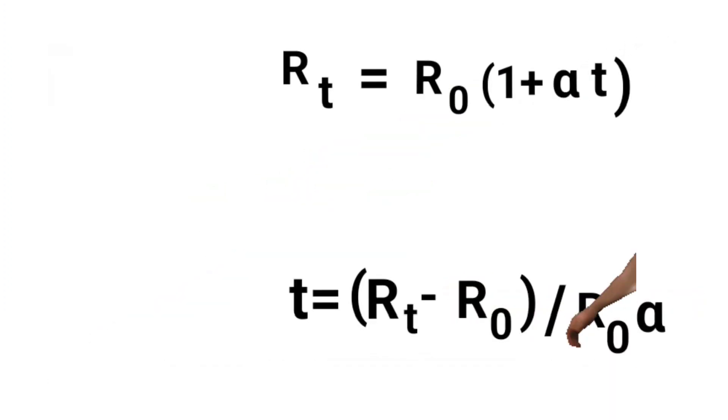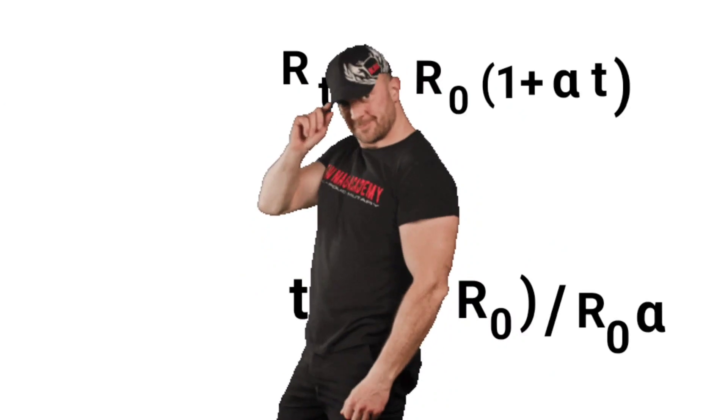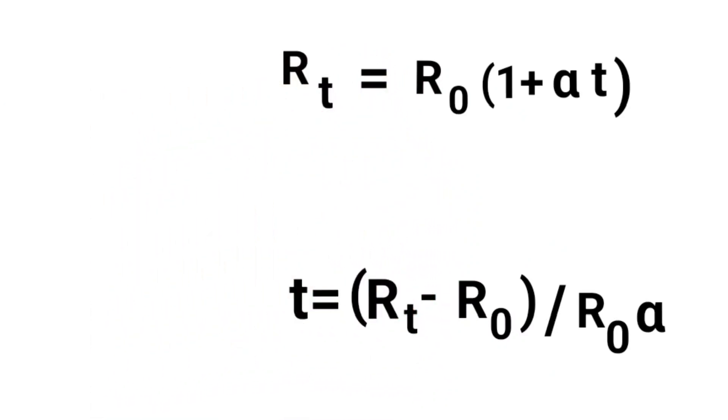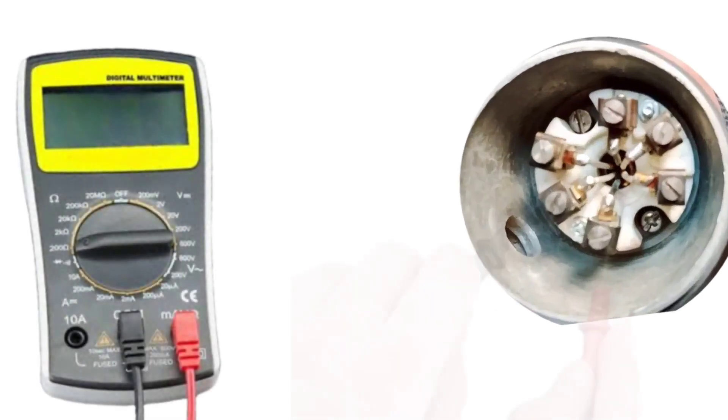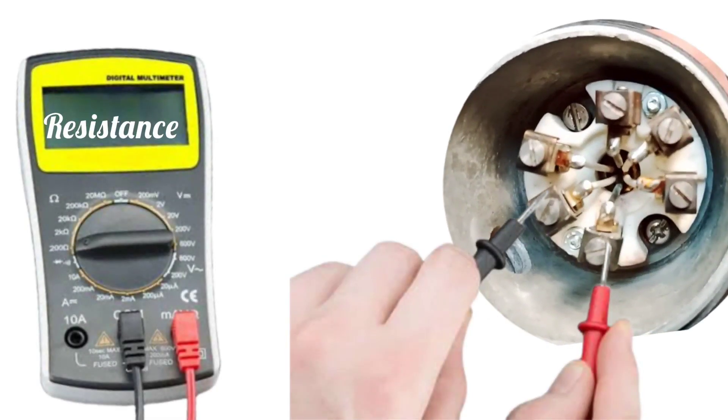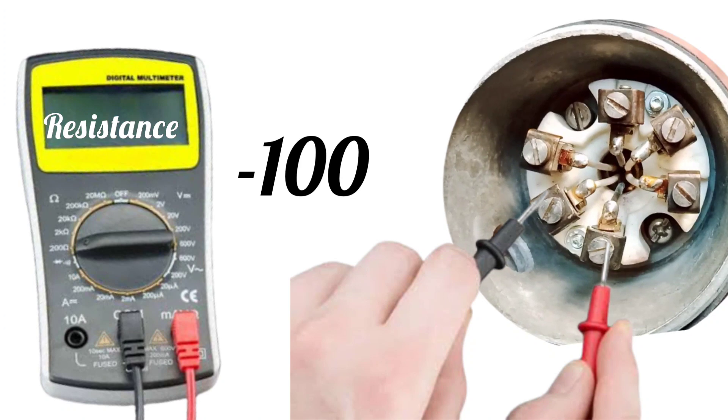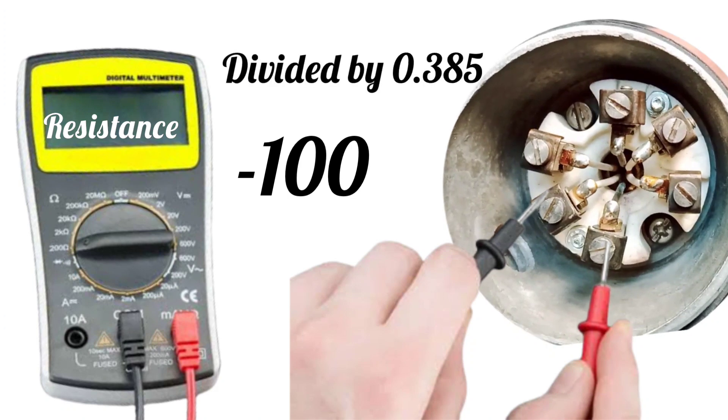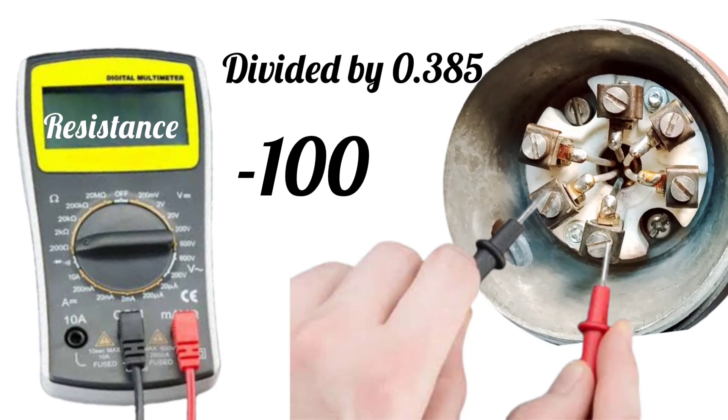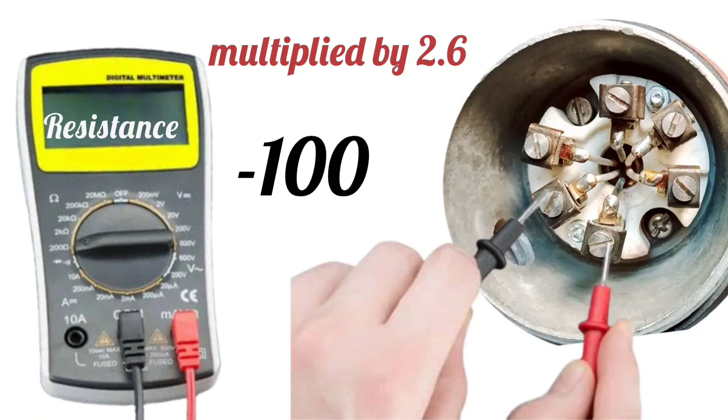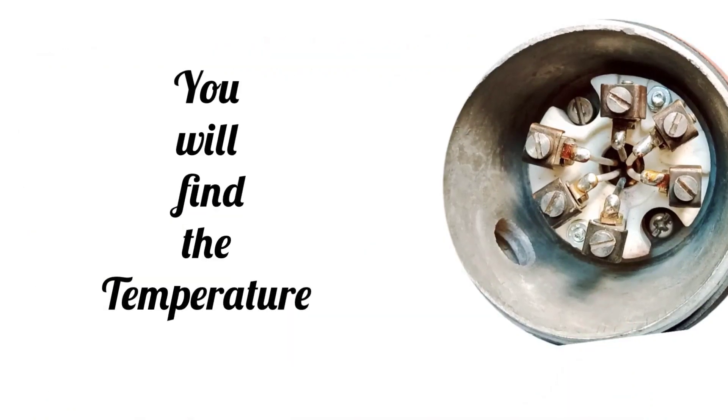Let us now understand the formula in easy language. There is no need to memorize long and elaborate formulas. As much resistance as being shown in the multimeter, minus 100 has to be done, and that has to be divided by 0.385, or multiply by 2.6. You will find the temperature.